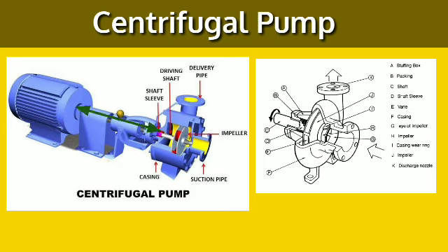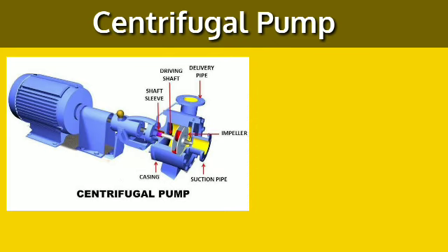When this shaft goes out from the casing, there is a stuffing box, because the liquid flowing inside the casing can escape from there. So there we need to seal it, and we seal it with gland packing. These gland packings are installed inside a box called the stuffing box. In newer types of pumps, this gland packing has been replaced by mechanical seal rings.